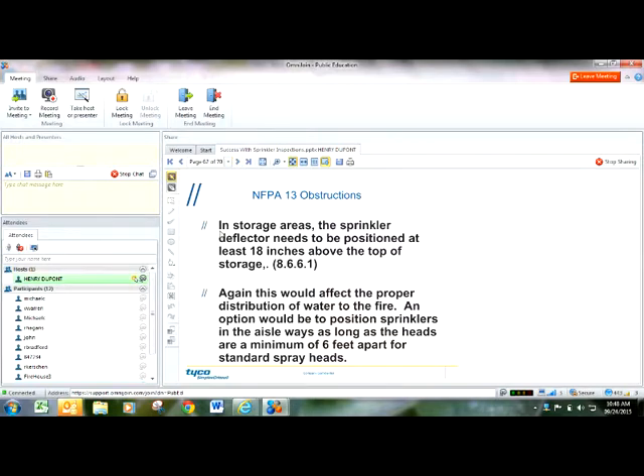This is a real big one. You see this a lot in long-term care, where you have a closet with a shelf in it, and there's a sprinkler head at the top of the closet. Well, you have to maintain 18 inches from the bottom of that deflector to the top of any storage. So if you're stacking stuff up on top of that shelf, and the storage gets within 18 inches of the deflector, that's a no-no. You have to either lower that storage or make them remove that shelf. And I would suggest removing the shelf, because they can lower the storage, and then the next tenant comes in and doesn't know, and then you've got the same issue.